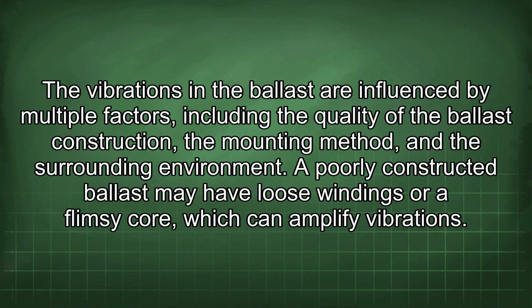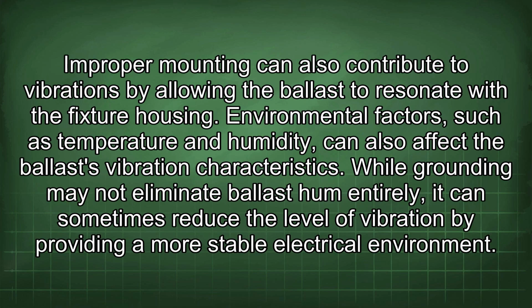The vibrations in the ballast are influenced by multiple factors, including the quality of the ballast construction, the mounting method, and the surrounding environment. A poorly constructed ballast may have loose windings or a flimsy core, which can amplify vibrations. Improper mounting can also contribute to vibrations by allowing the ballast to resonate with the fixture housing. Environmental factors, such as temperature and humidity, can also affect the ballast's vibration characteristics.